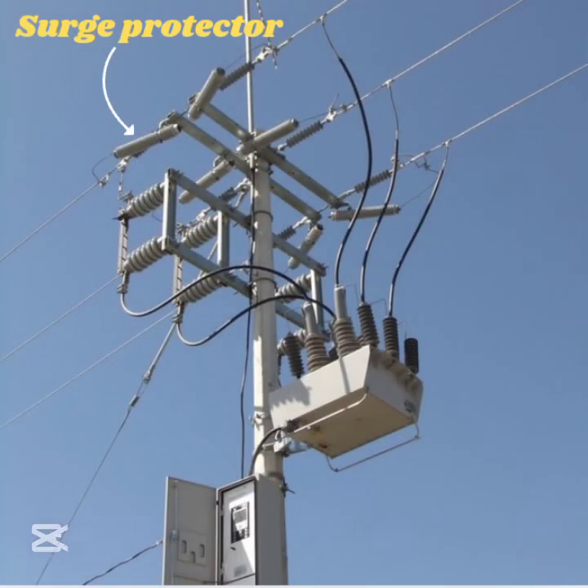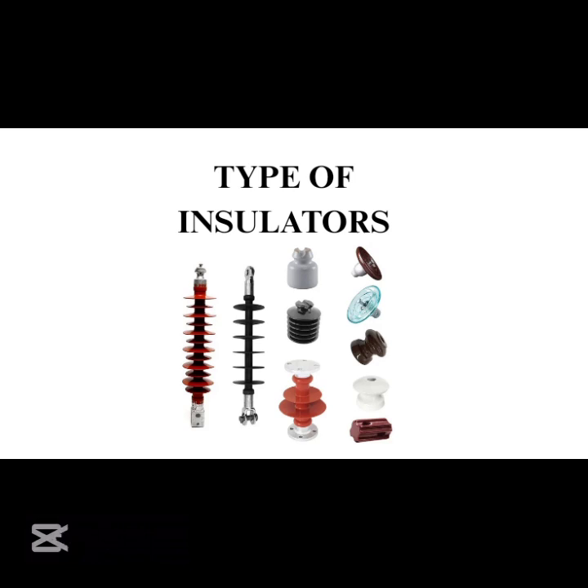Number 4. Surge protectors. Surge protectors are devices installed at substations and distribution points to safeguard electrical equipment from voltage surges. They work by limiting the voltage surge to a safe level, preventing it from reaching sensitive equipment. Surge protectors can be designed to handle various levels of surges, and are crucial in protecting transformers, switchgear, and other critical components. Number 5. Insulation coordination.